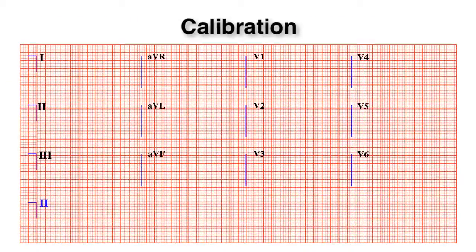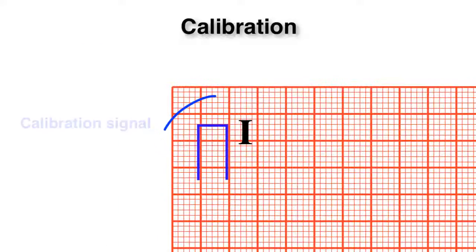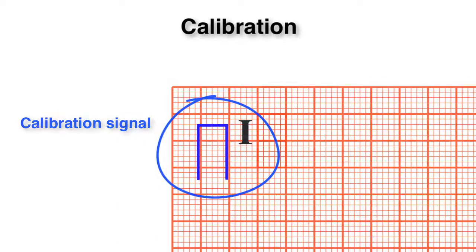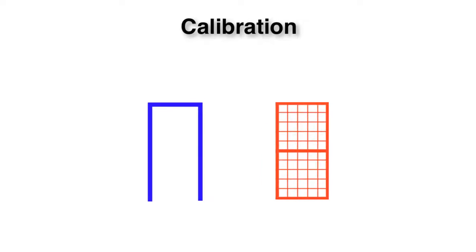And finally, just a little word on calibration. A standardization mark or calibration signal can be seen on every EKG. The EKG must be properly calibrated so that a 1 millivolt signal produces a 10 millimeter deflection.